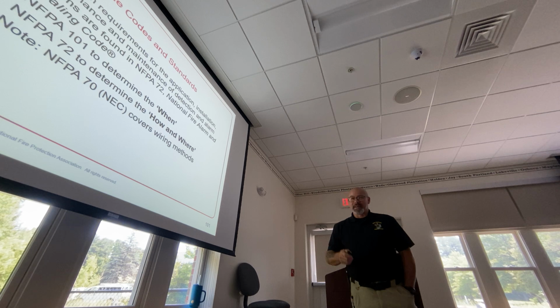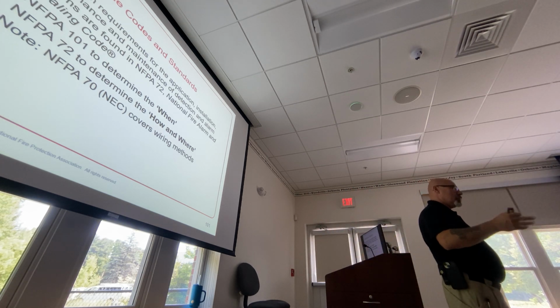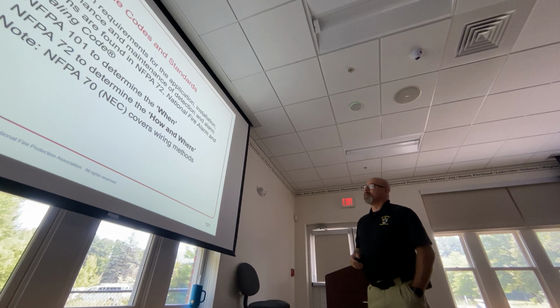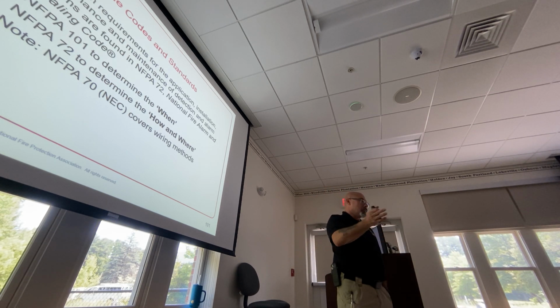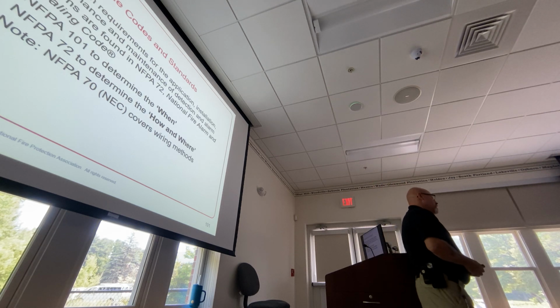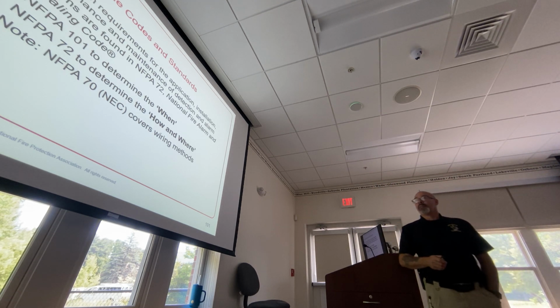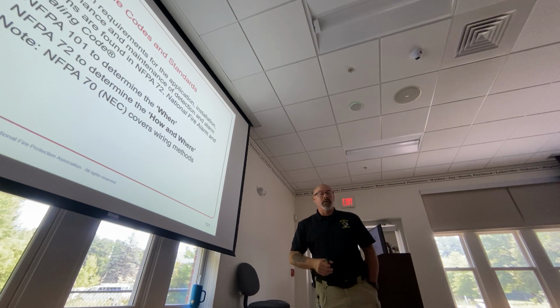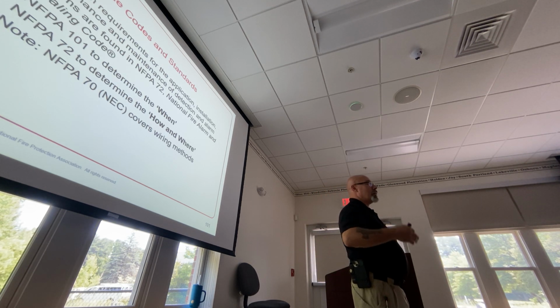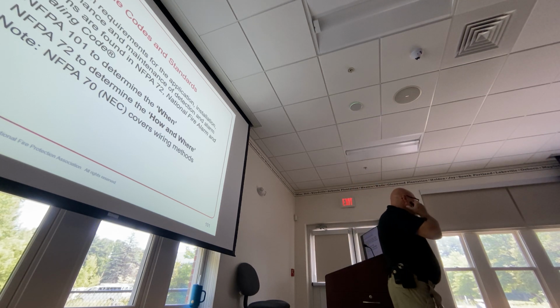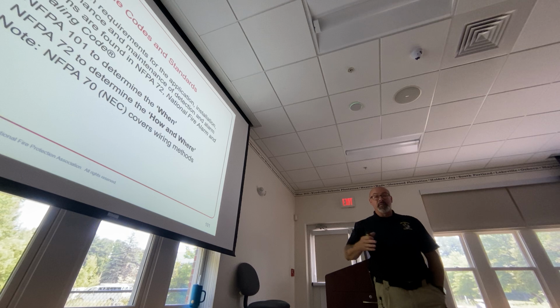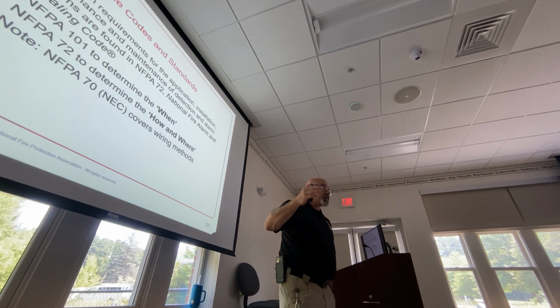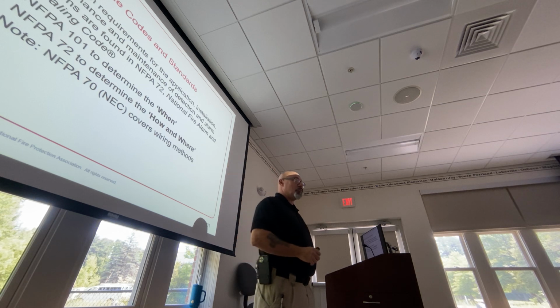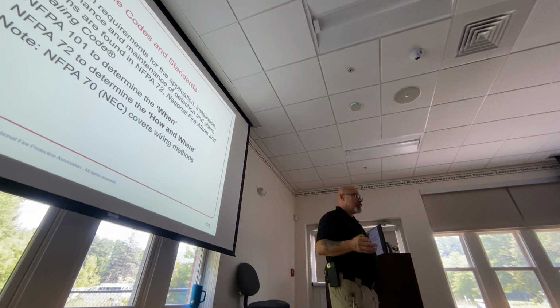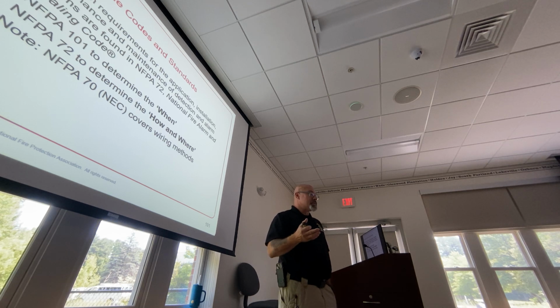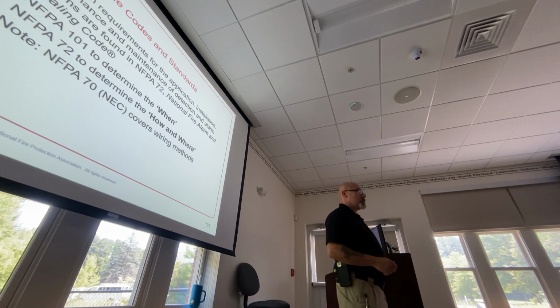Okay? Like I said, NFPA 101 or local ordinances will dictate when a fire alarm system, or going backwards to a sprinkler system, may be required in a building. NFPA 72 determines the how and where. How do I install it? Where do I install it? How do I do inspection, testing, maintenance of it? Different than the NFPA 13, different than sprinklers. Sprinklers has its own inspection and testing maintenance book, which is NFPA 25. Fire alarms and detection systems utilize the same book. NFPA 72 covers everything, covers both.